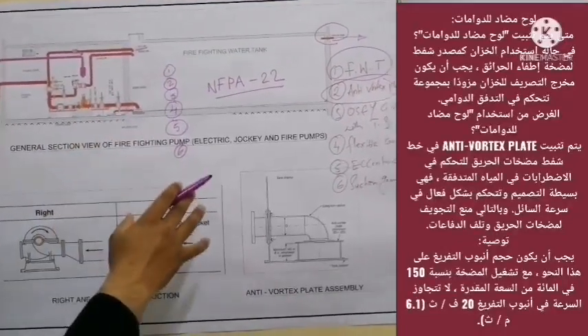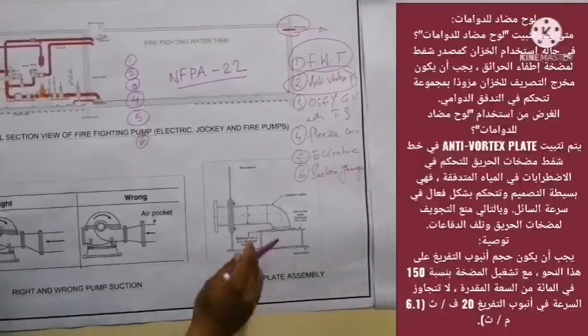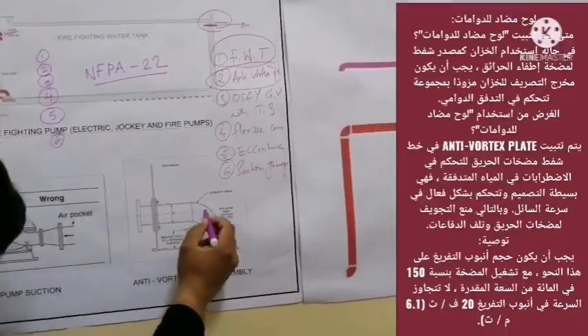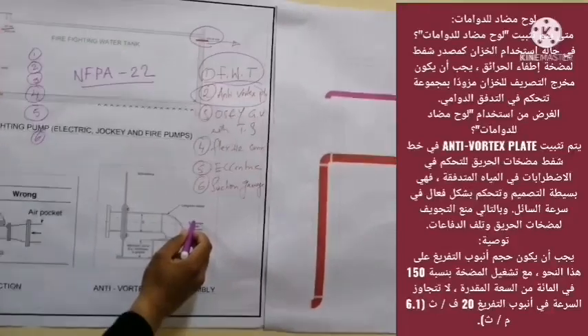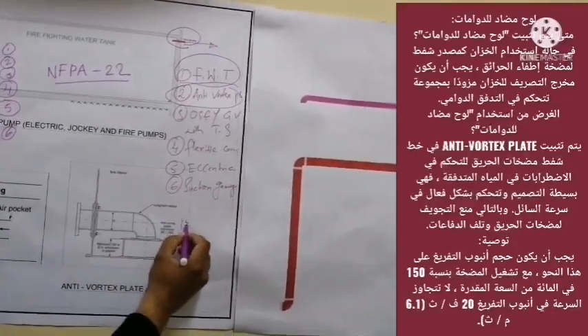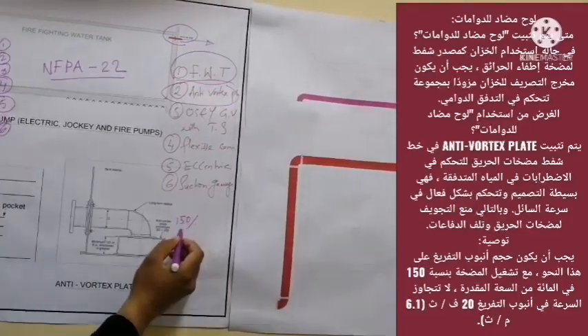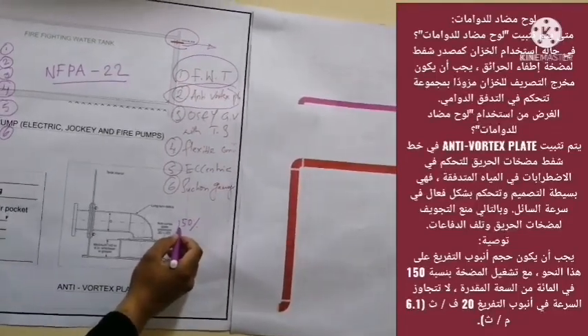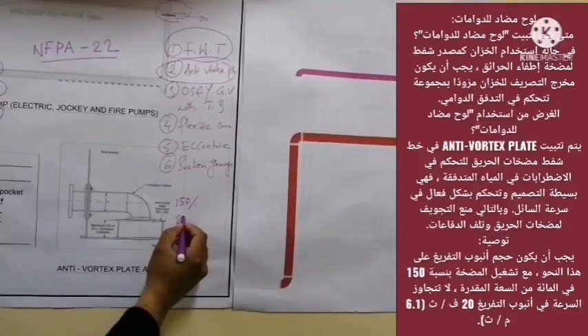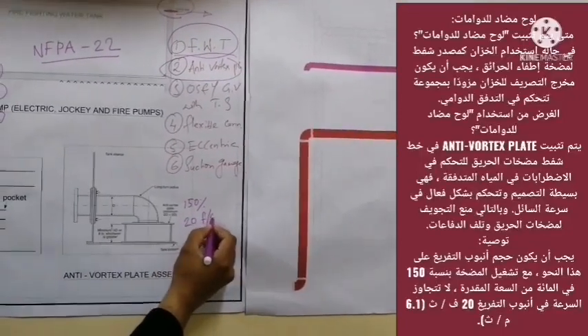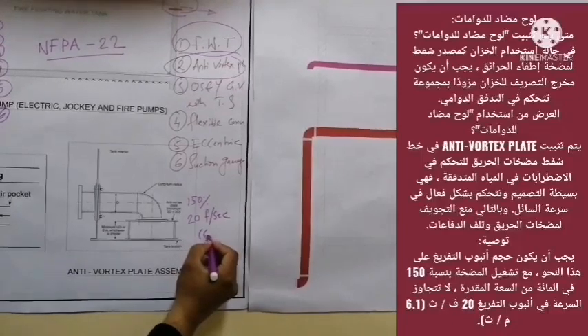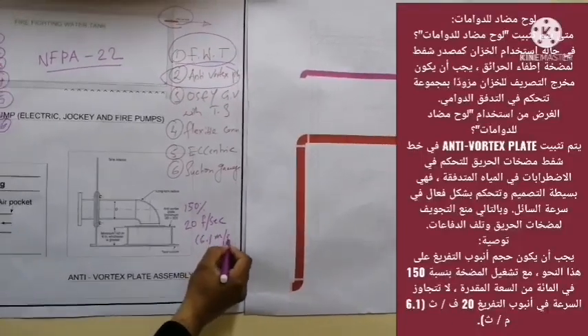Regarding the discharge pipe: the discharge pipe size shall be such that with the pump operating at 150 percent of rated capacity, the velocity in the discharge pipe does not exceed 20 feet per second, which is 6.1 meters per second.